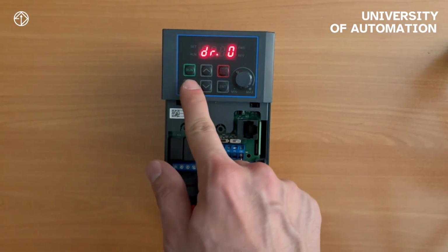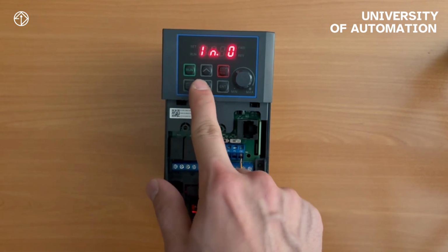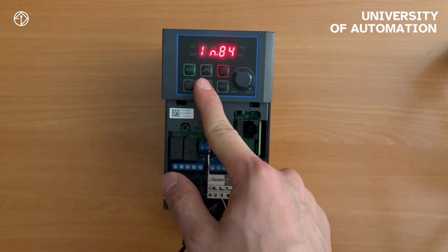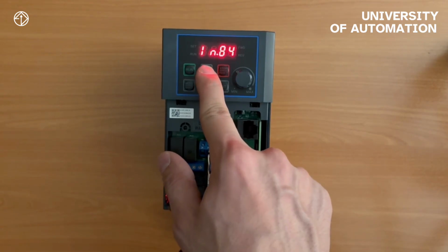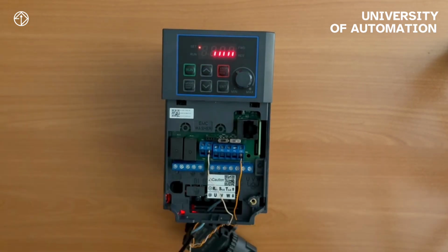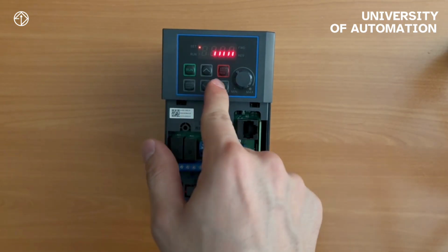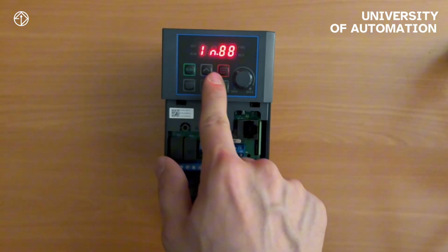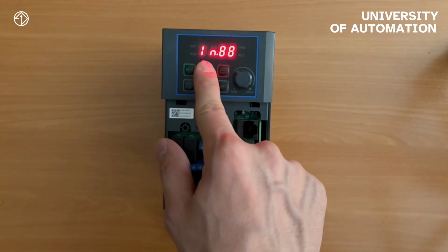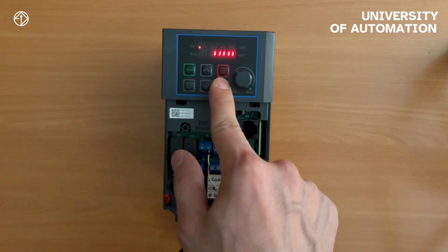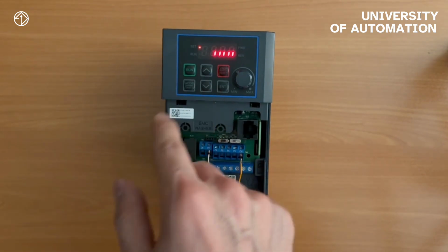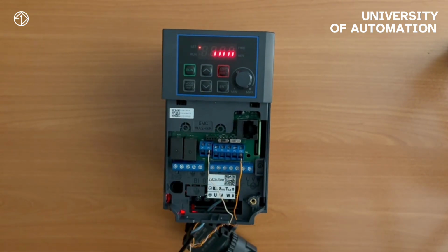Parameter 87: we can precisely determine whether the various digital inputs are configured as normally closed or alternatively as normally open circuits. We said that sometimes, like in emergency situations, we absolutely require our digital input to be configured as normally closed in its initial state. This is a critical setting. However, regarding parameter 90, we previously established that we can make certain adjustments or modifications to its behavior, potentially impacting this initial configuration. The status of the digital inputs.